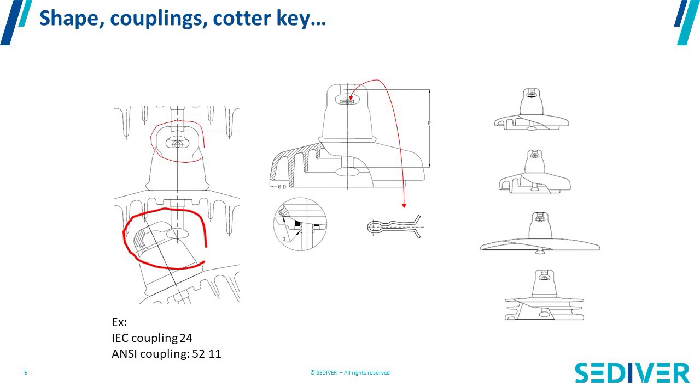Well, since I was talking about desertic environments, you have usually in deserts dust and mostly nothing else but dust. The idea of the third insulator from the top is a flat disc with no ribs. Why? Because if you have dust, dust is going to come on those insulators and the wind will clean up progressively as it goes the dust from the surface of the insulator, so it remains cleaner than if you had ribs where the dust is going to stay stuck between. This insulator is typically what is being used in desertic environments.